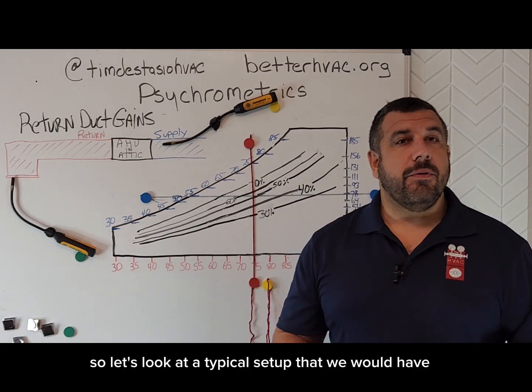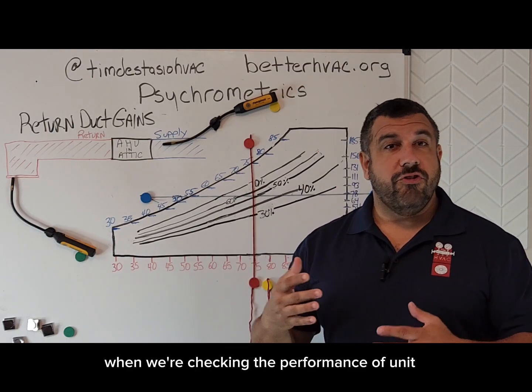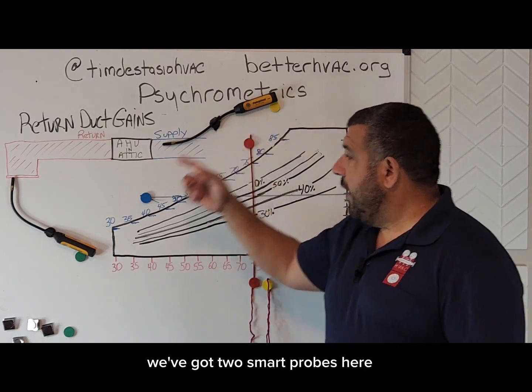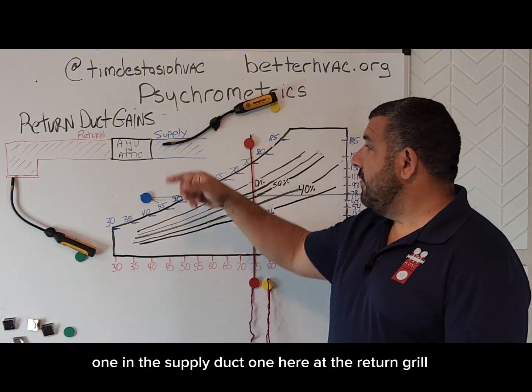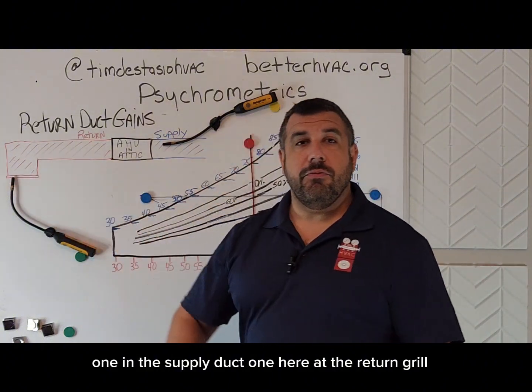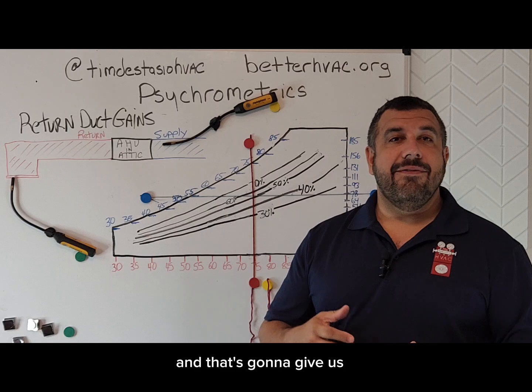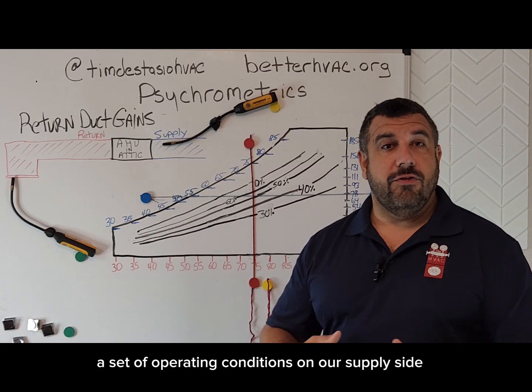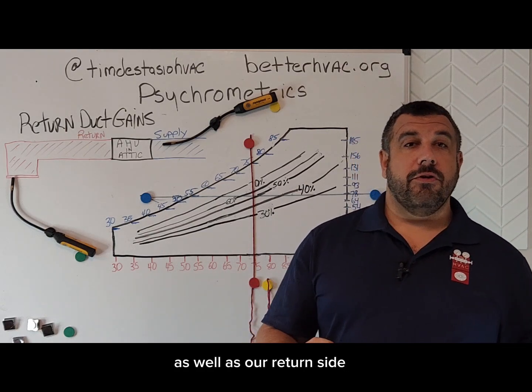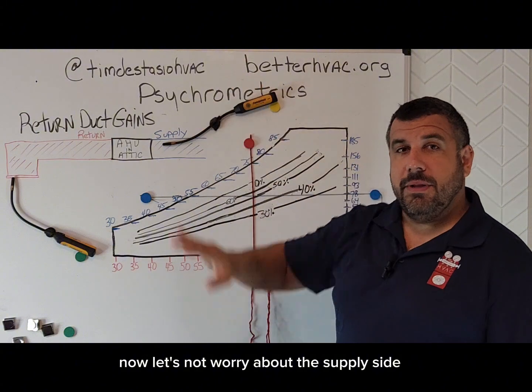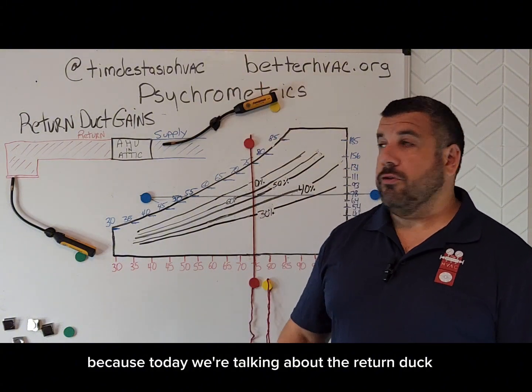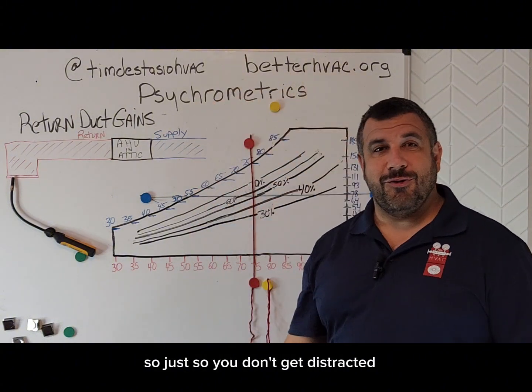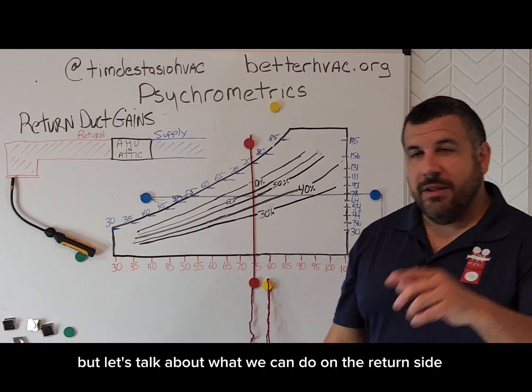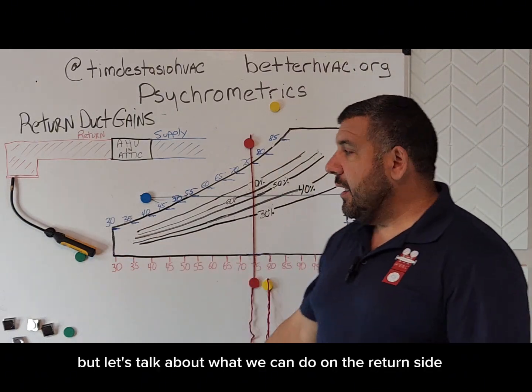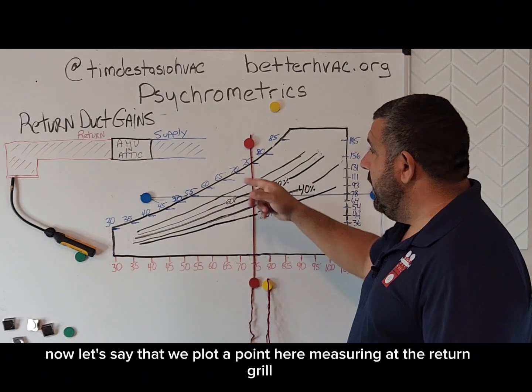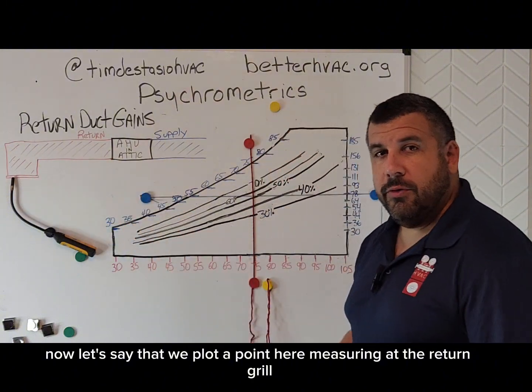So let's look at a typical setup that we would have when we're checking the performance of a unit. We've got two smart probes here, one in the supply duct and one here at the return grille. And that's going to give us a set of operating conditions on our supply side as well as our return side. Now let's not worry about the supply side because today we're talking about the return duct. So just so you don't get distracted, we'll get rid of that one. But let's talk about what we can do on the return side.